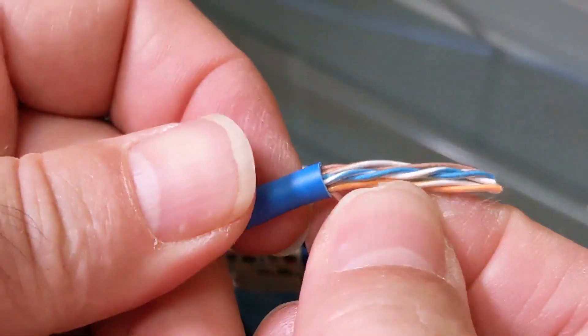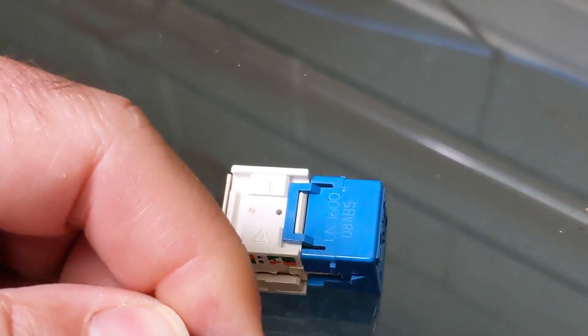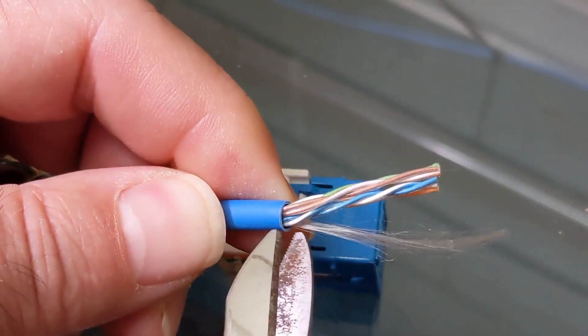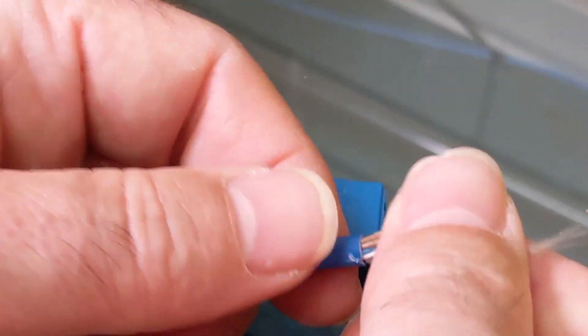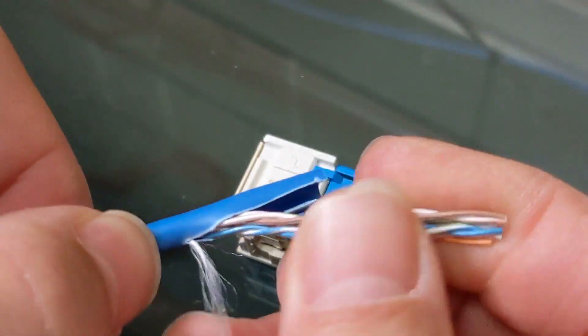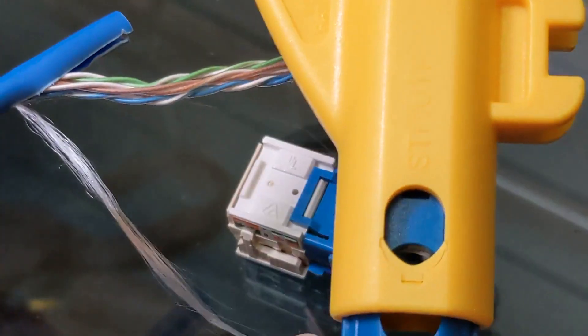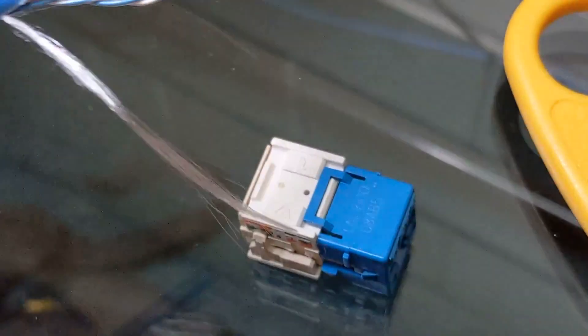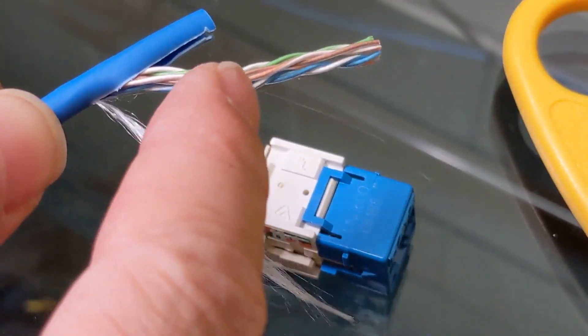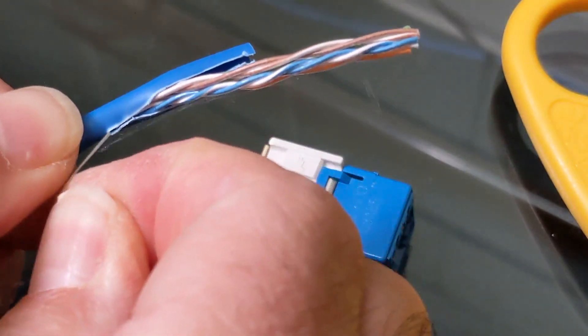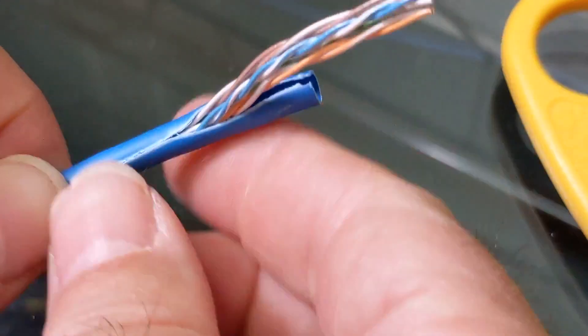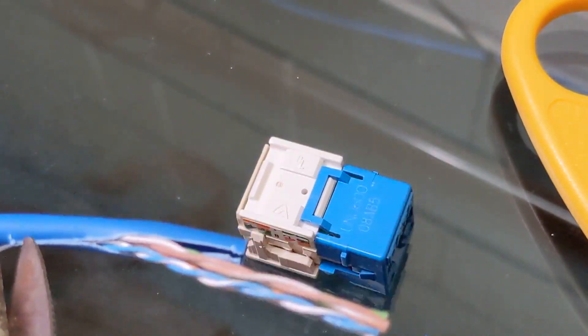Now what you're supposed to do is, after you make that initial little cut, make a little bitty nick like this, and take the pull string and pull back some of the jacket. You might be thinking, why are we doing that? Well that's because if there's any chance that either the wire stripper or the electrician scissors might have nicked the insulation on these wires, we want to go ahead and pull back and get to a fresh spot where that won't be an issue. So you pull the string back, it kind of acts like a little peeler.